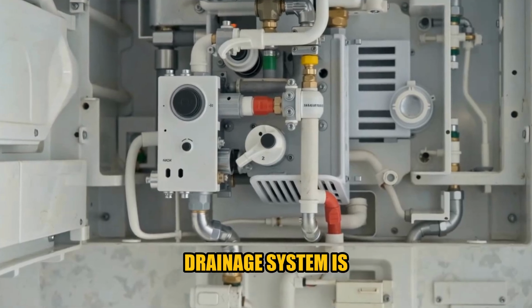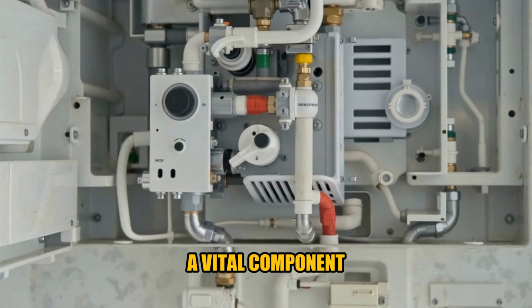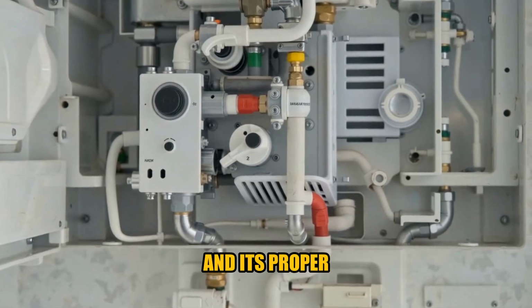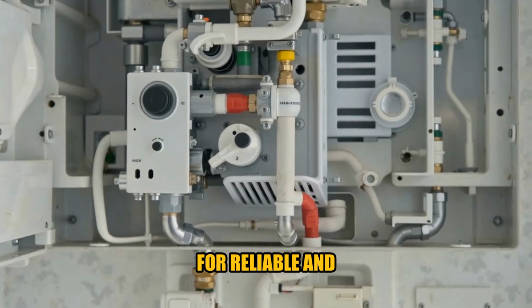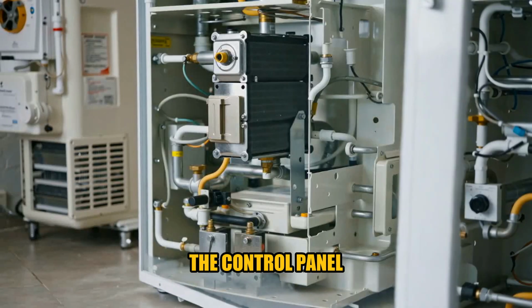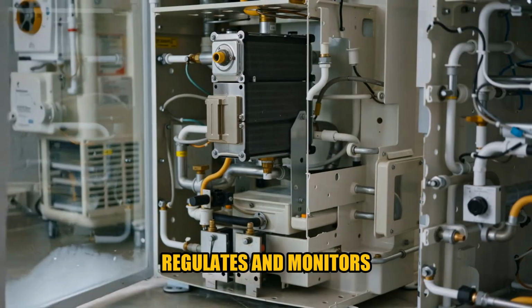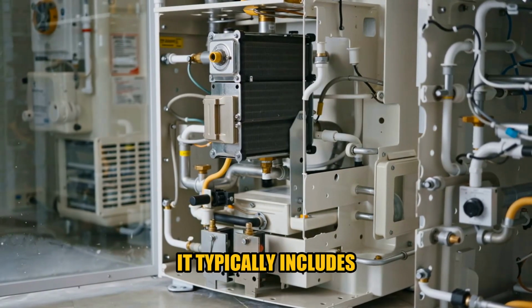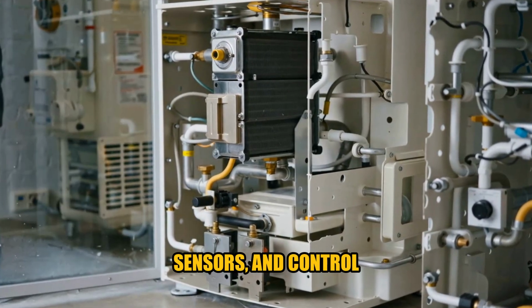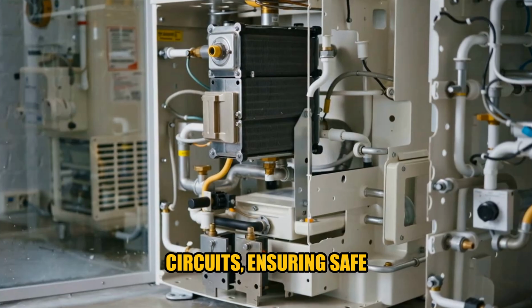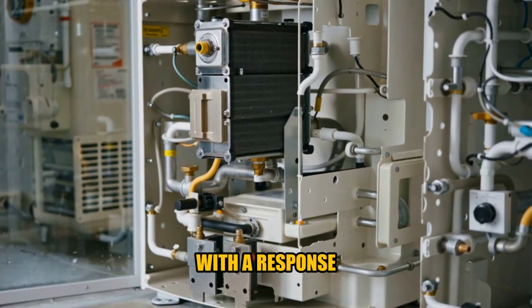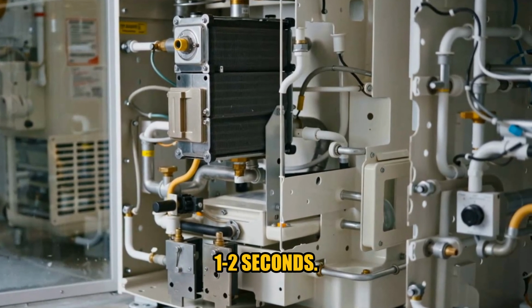efficiency and preventing damage. The condensate drainage system is a vital component of the boiler, and its proper function is essential for reliable and efficient heating. The control panel regulates and monitors the boiler's operation. It typically includes a user interface, sensors, and control circuits, ensuring safe and efficient operation with a response time of around 1 to 2 seconds.